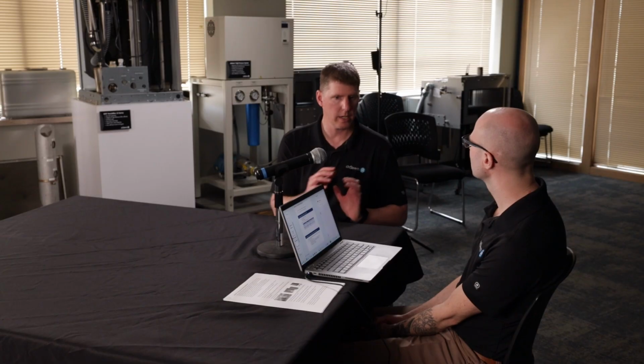What you have to consider as a designer, though, is how the air is moving through it. We talked about that blank off portion. You have to allocate that system effect, and how that's done is another piece you have to add, along with the air velocity going through it. We can't plan if you're going to taper it nicely into the airstream to minimize that pressure drop, or if it simply hits a wall and has no choice but to turn into that dispersion device.